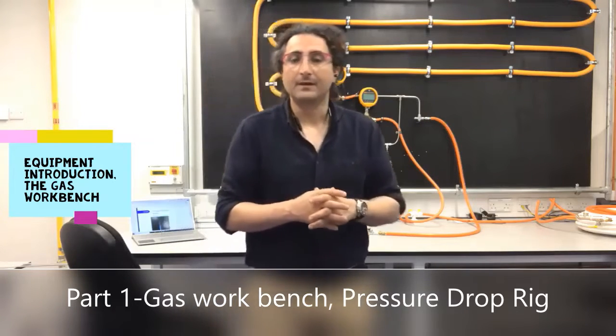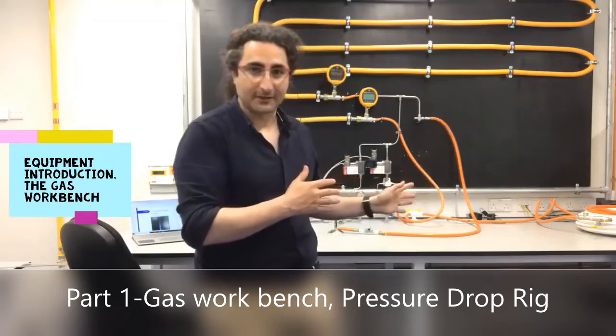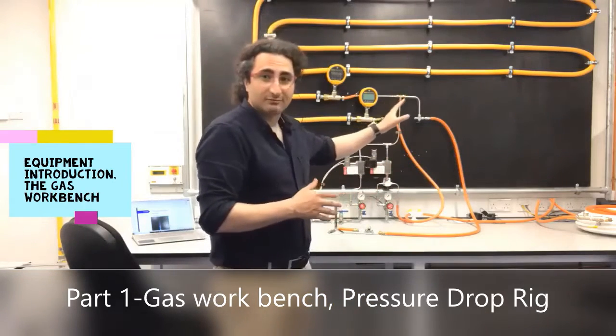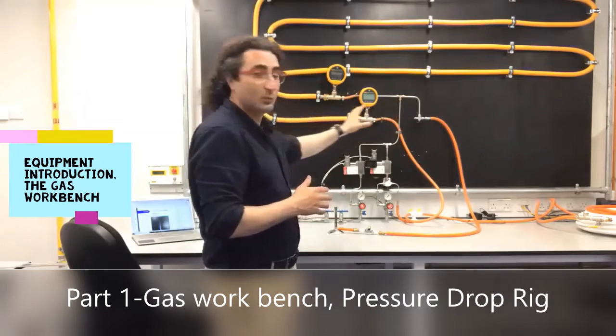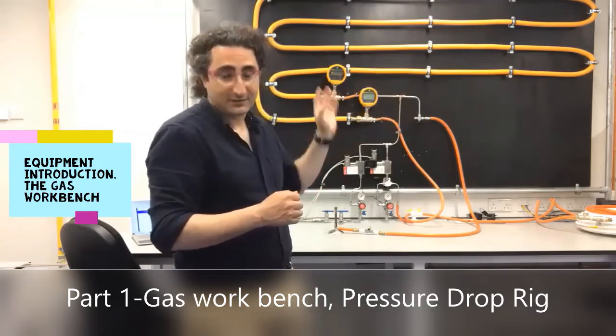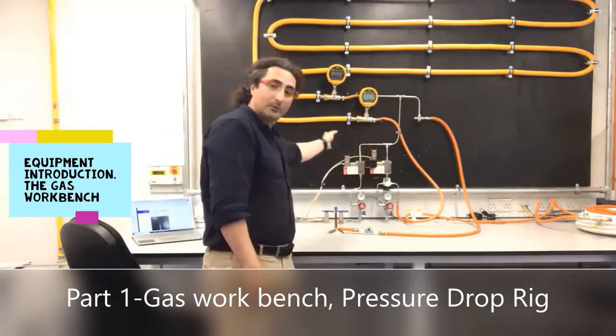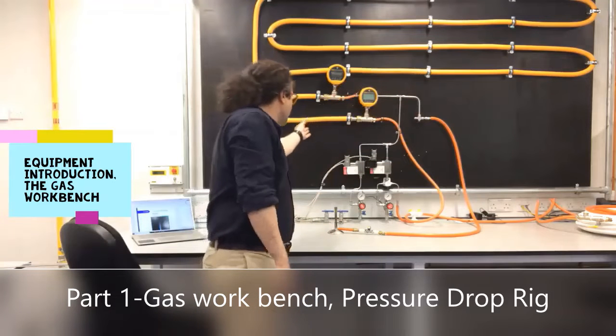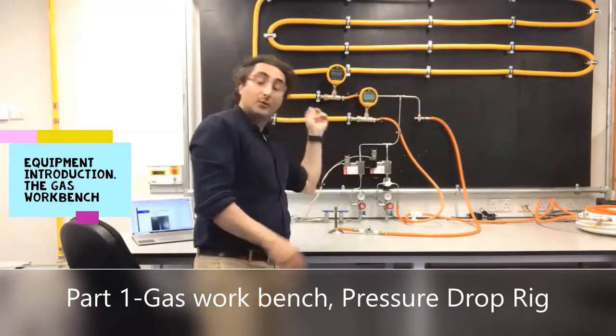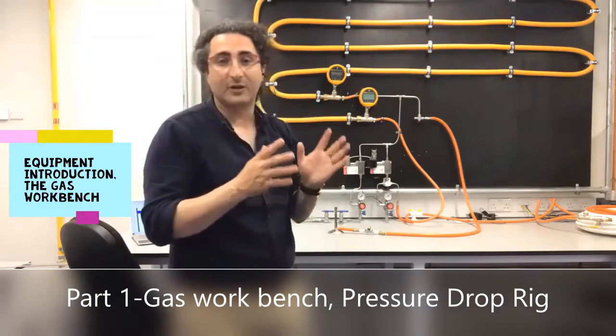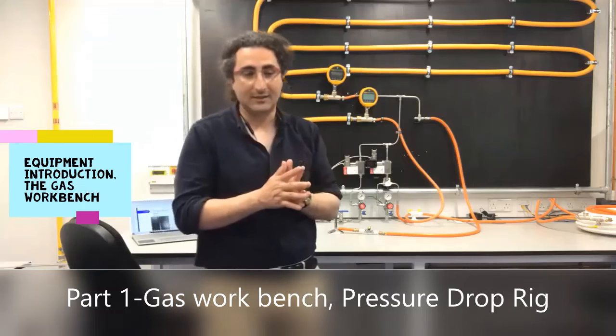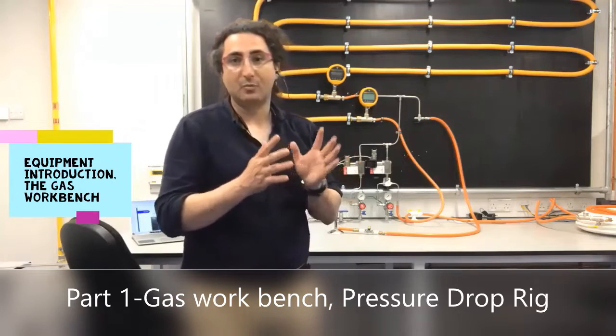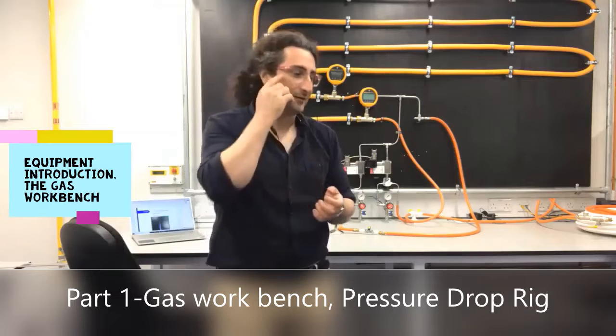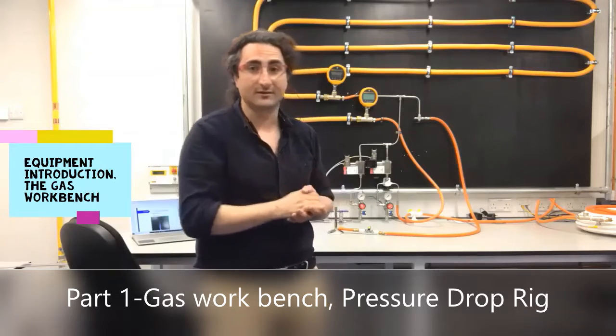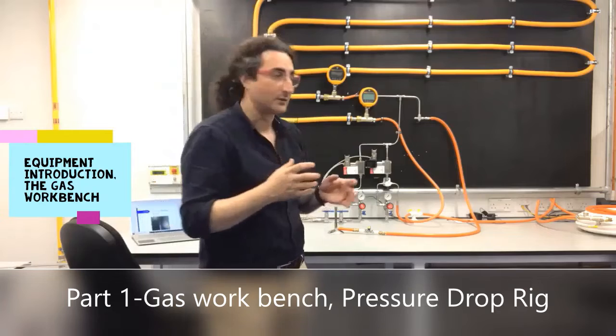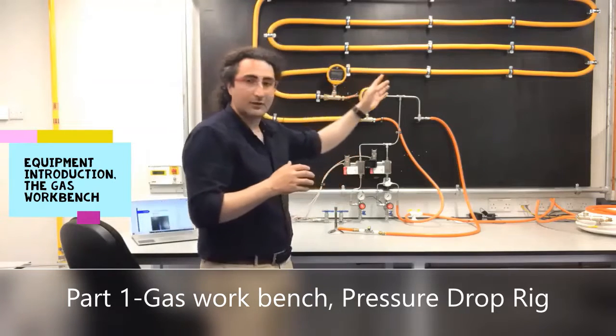So let's start with this pressure drop rig. We designed this pressure drop rig. We tried to make it colorful. First of all, whenever you see a pipe with the yellow color, it means that we have gas there. We have natural gas. The symbolic color for natural gas is yellow in code and standard. So this is designed for natural gas.